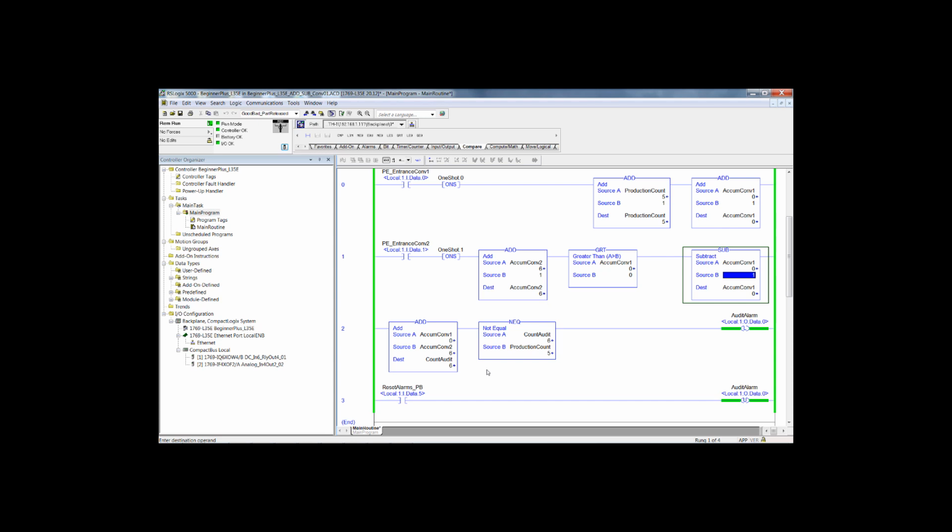How could an object leave conveyor 1, pass through the photo eye onto conveyor 2 if conveyor 1 is empty? It cannot. Therefore, if the photo eye on conveyor 2 is blocked, incrementing conveyor 2 count and attempting to decrement the count on an empty conveyor 1, that is a problem. How can we edit our logic to address that? What can we do about it to avoid the problems that it might create? Or will our existing logic raise the alarm if this scenario occurs?